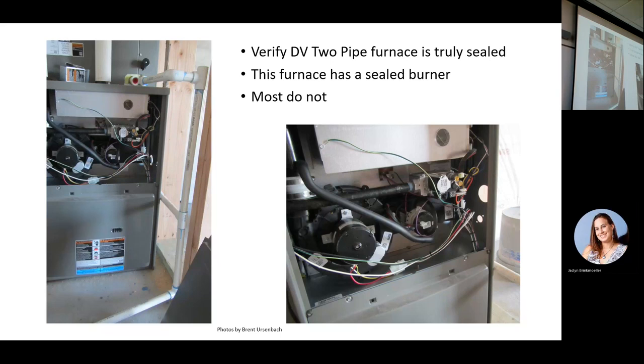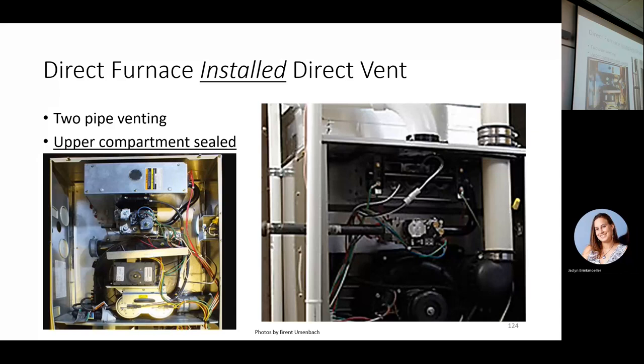And they're not relying on the upper door to seal the burners. If we go to a lot of furnaces nowadays, rather than the sealed burner compartment, you can see the burners right there, and we have to rely on the door and a gasket. But what's the other critical thing? All the penetrations into that upper compartment have to be sealed.